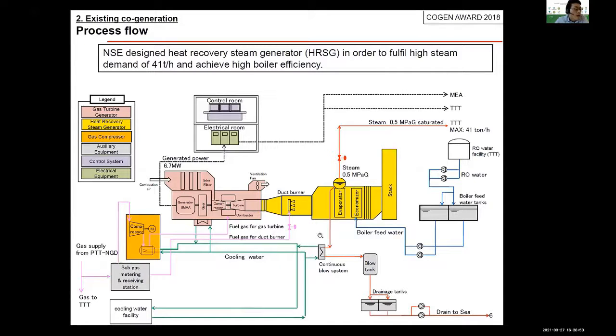So that's why we designed the heat recovery steam generator in order to fulfill a high steam demand of 41 tons per hour and achieve a high boiler efficiency. In this JCM project, we modified this heat recovery steam generator. To be specific, we installed an additional heat exchanger in between the economizer and the stack.